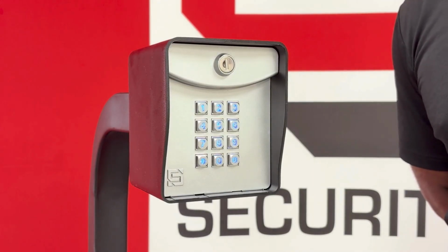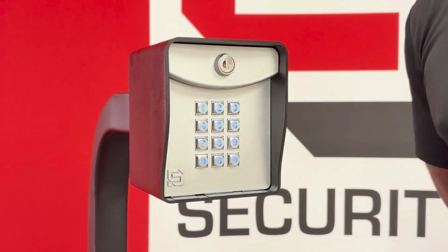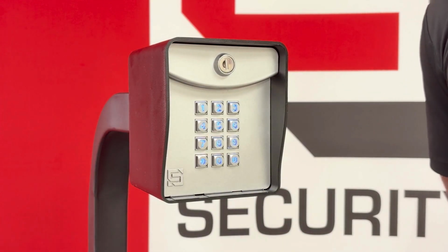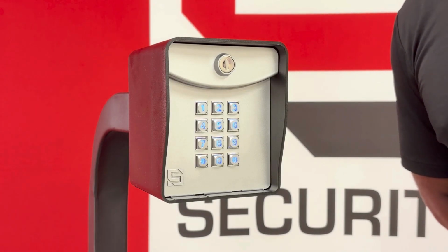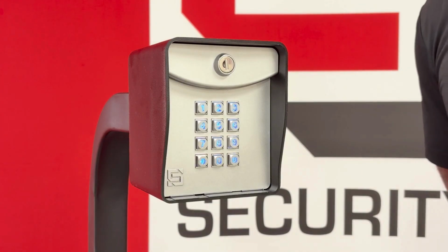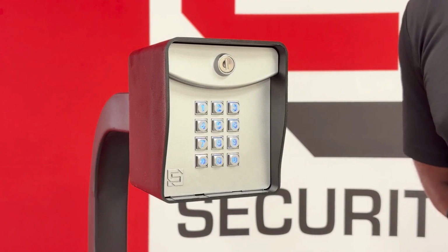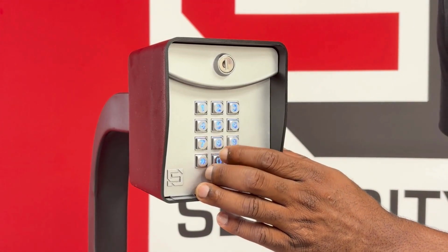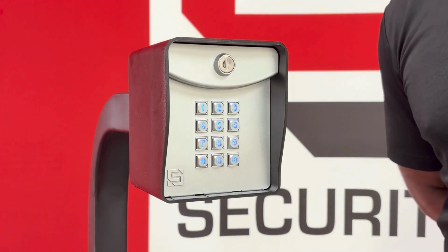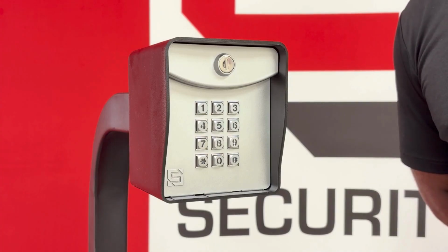Then we're going to select the channel that we want to use, which is typically going to be channel A. So we'll select 1. And then we can go ahead and enter the number of seconds that we want the relay to fire, any 4-digit number. So in this case, I'm going to put it for 5 seconds. So I'm going to enter 0005. Now we'll enter pound to exit out of programming mode. And now when a code is used on channel A, the relay will fire for 5 seconds. You're all set.